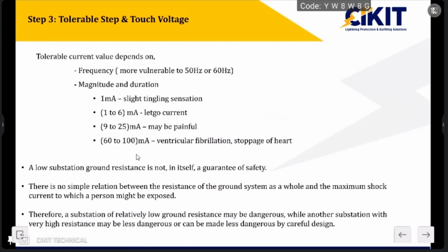So the third step is the tolerable step and touch voltages. Why are we giving much more importance to step and touch voltages? Our human body is more sensitive to currents of 50 to 60 hertz frequency. Our body will show some more resistance towards DC current. At the same time, if the frequency is lower or higher, our body will also show some more resistance. But our body is more vulnerable to 50 hertz frequency.